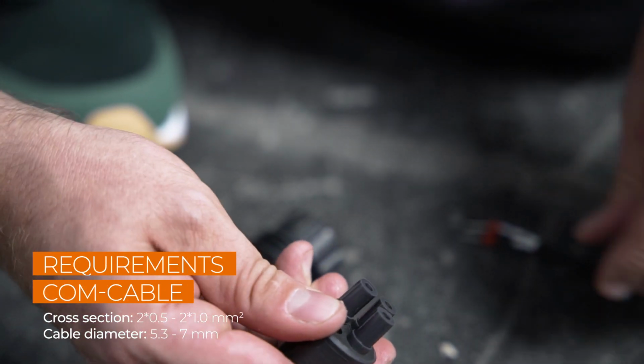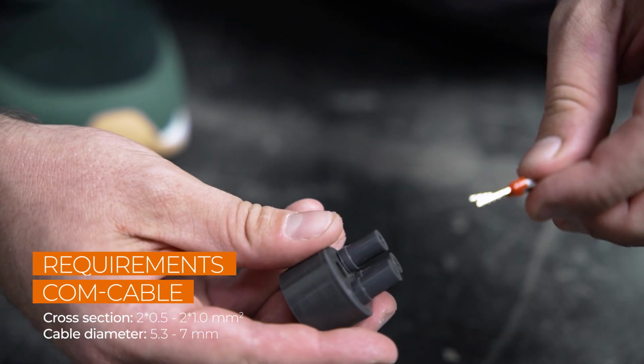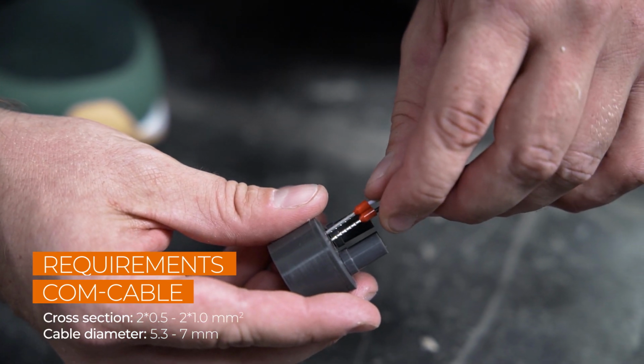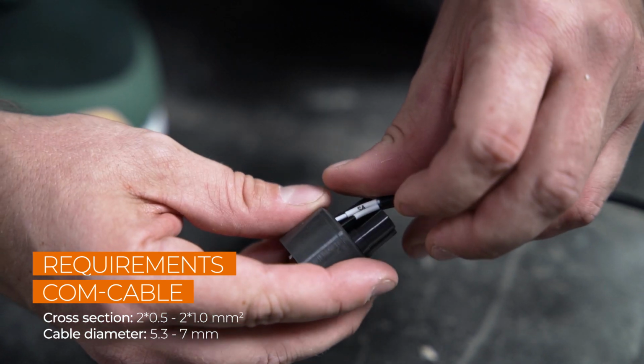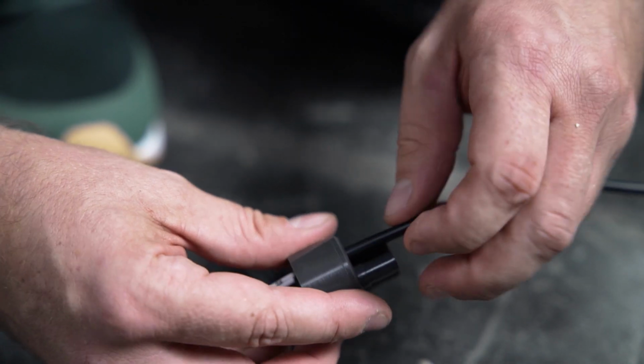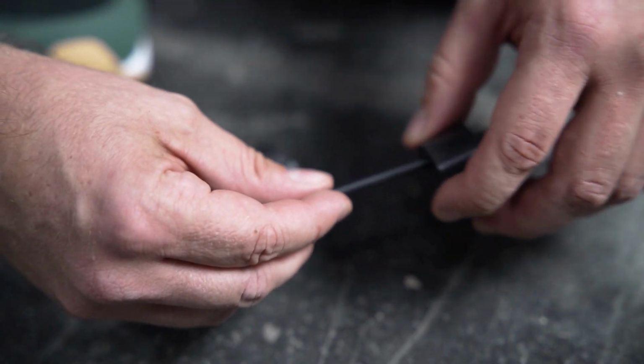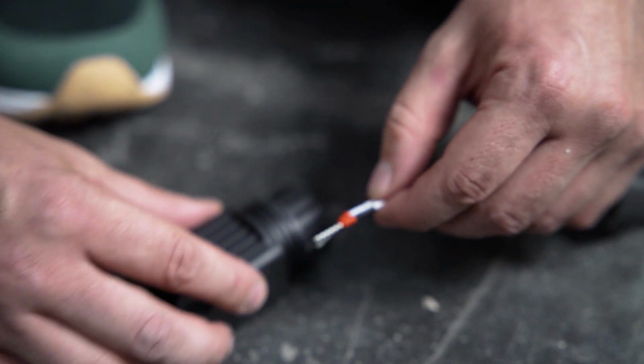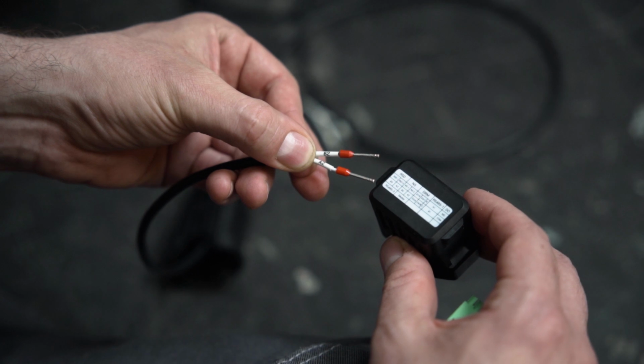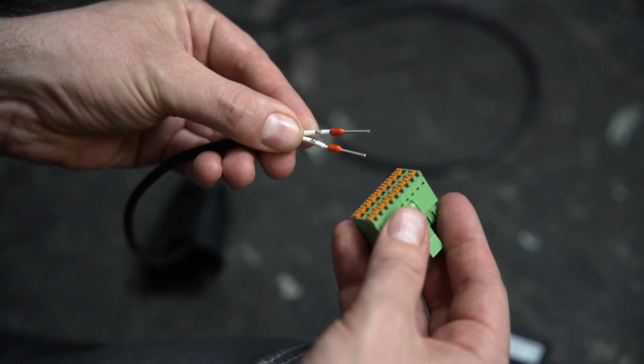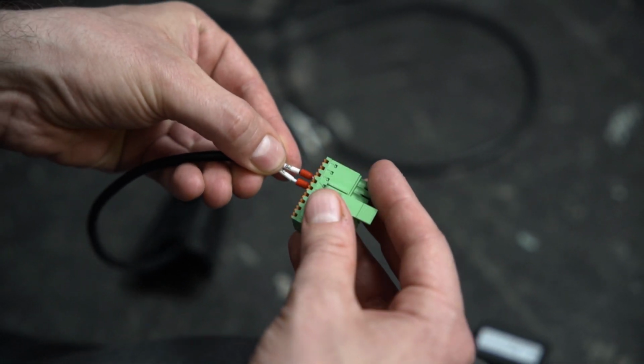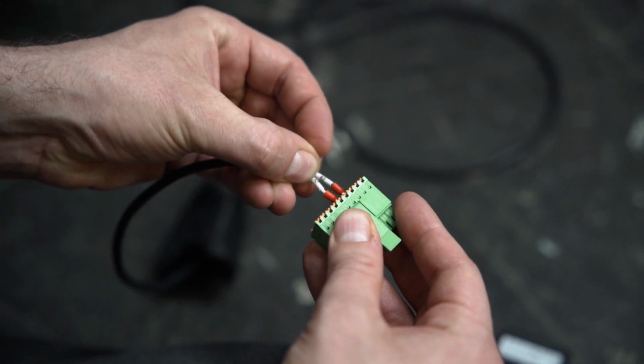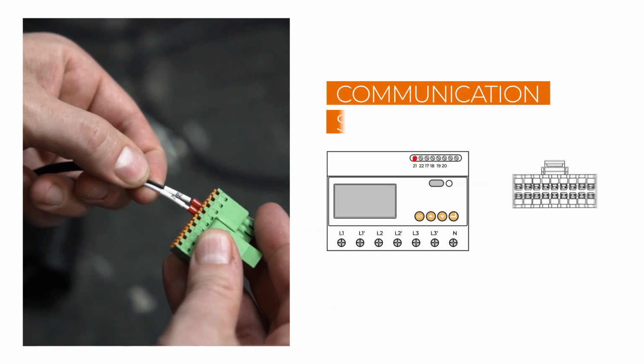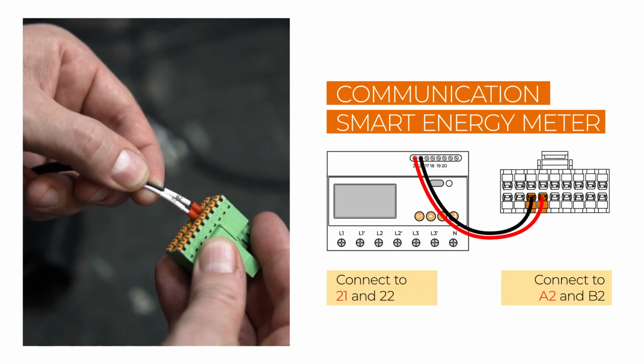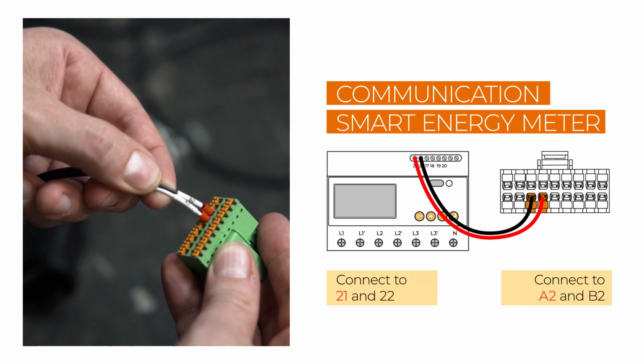Via this port, you can connect the smart energy meter or the communication cable for daisy chain mode. Let's start with the energy meter, which is needed for the feed-in power function. Remove approximately 4 to 5 centimeters of the cable sheath of the communication cables. Then strip approximately 7 to 10 millimeters off the inner cables. If necessary, you may have to fit the cables with end sleeves before you push them into the plug. The smart meter is connected to the ports A2 and B2.